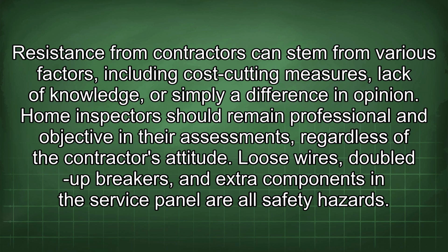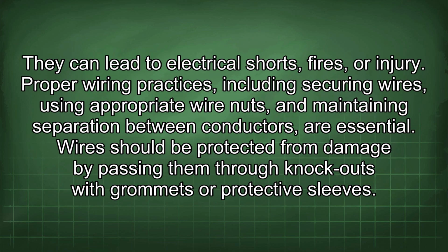Loose wires, doubled-up breakers, and extra components in the service panel are all safety hazards. They can lead to electrical shorts, fires, or injury. Proper wiring practices, including securing wires, using appropriate wire nuts, and maintaining separation between conductors, are essential. Wires should be protected from damage by passing them through knockouts with grommets or protective sleeves.